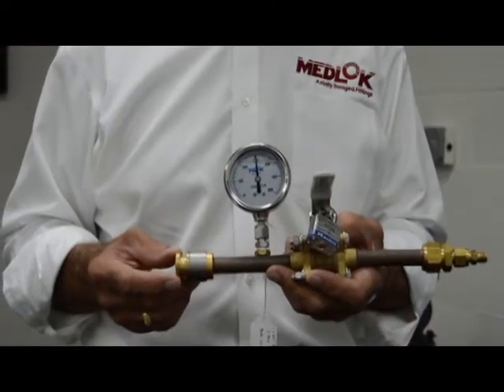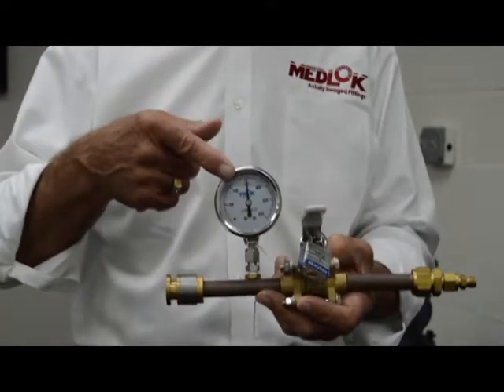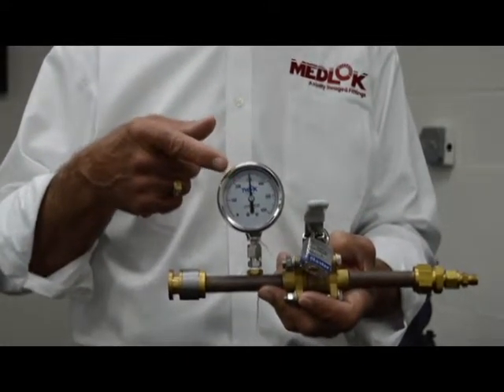Here's another example of the reliability of the Medlok fitting. We've had this pressurized at 300 psi for 9 months without any pressure decay.